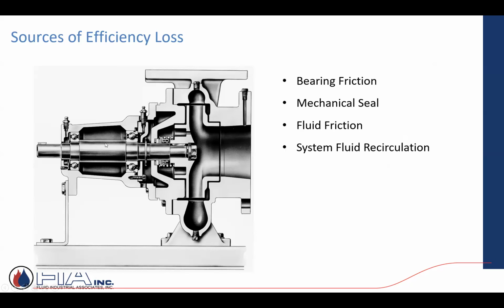Quick picture just saying, hey, this is a picture of a pump, the wet end. I have my impeller, I have my shaft, I have my seal, I have my volute. Here's my bearing assembly and my coupler behind it. What are my losses? Bearing friction, mechanical seal. There's rubbing as it's rotating at 1800. There's some frictional loss. There's fluid friction inside the volute. There's a little bit of that recirculation.